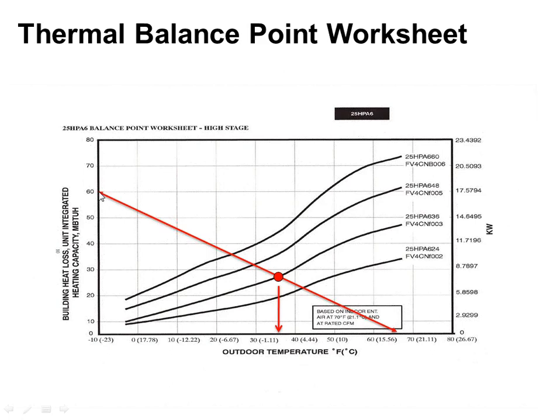Then we have to plot one other point on this chart. So you could do another load calc, but set it for 10 degrees outside or something, and get this 45 degree point. And once I have 2 points, I can draw a straight line through them and see what would happen at pretty much any outdoor air temperature. So in this case, at 65 degrees outside, this guy doesn't even need any heat for his house at all. He basically needs 0 BTUs at that point. So by looking at that, I can plot that on the same chart that has the heat pump capacities that are published by the manufacturer.